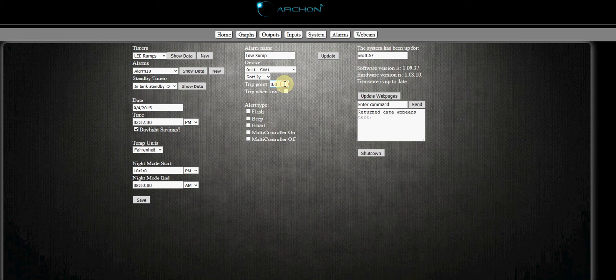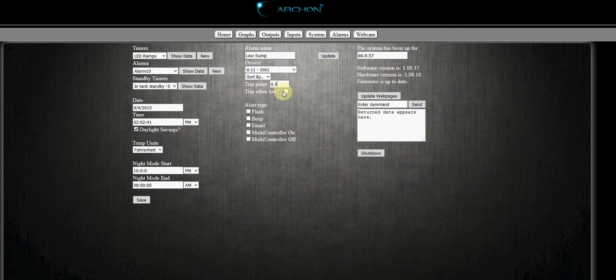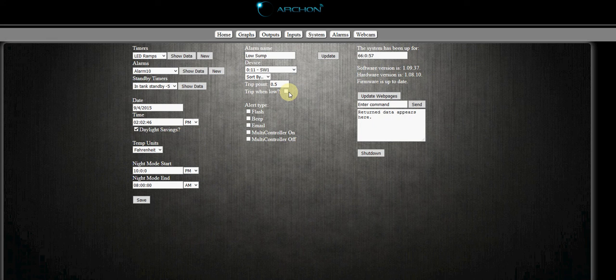And like I said, open is a one, closed is a zero. So we're actually gonna leave this, we're gonna put it right in the middle at 0.5. And I want it to trip when the switch is open, meaning the switch is one, so it's higher than this number. So we're gonna leave this unchecked.